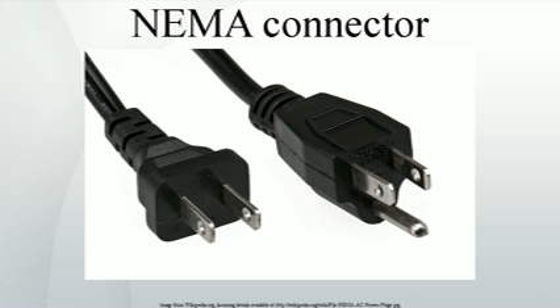Cheater plug adapters allow a three-prong grounded NEMA 5-15 plug to be mated to a non-grounded NEMA 1-15 socket. The adapters include a spade lug to allow connecting to ground, often via the cover screw used to attach the socket faceplate. NEMA standards exist for 1-15P, 1-20P and 1-30P plugs, and the 1-15R receptacle. There are no 1-20R and 1-30R receptacles, because 1-20P and 1-30P can mate with a corresponding NEMA 5 receptacle.